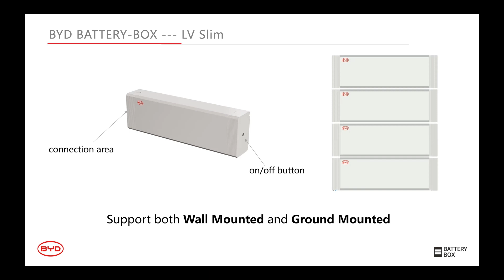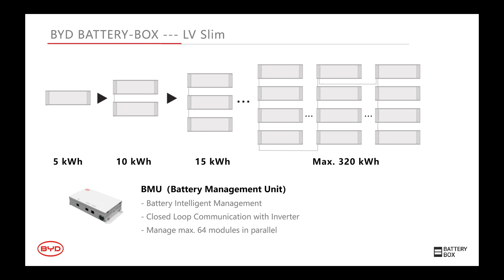It also has an external component, the BMU, battery management unit, for the whole system. The function of the BMU is battery intelligent management and closed-loop communication with the inverter. One BMU can manage a maximum of 64 modules in parallel, which helps customers save cost. So no matter if you need 1 LV Slim or 5, 15, or 50 LV Slim units, you only need 1 BMU for the whole system, and it can do closed loop communication with the inverter.